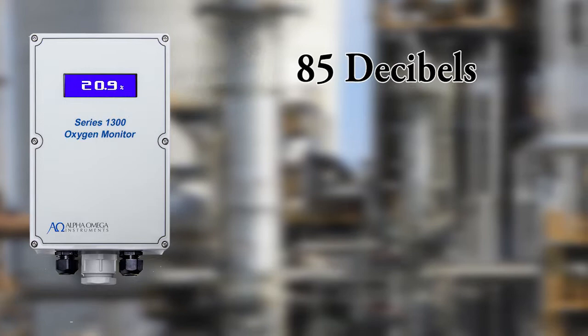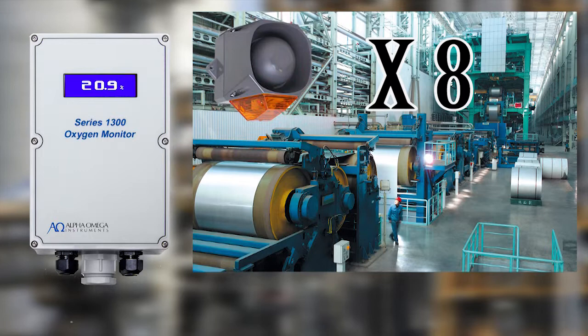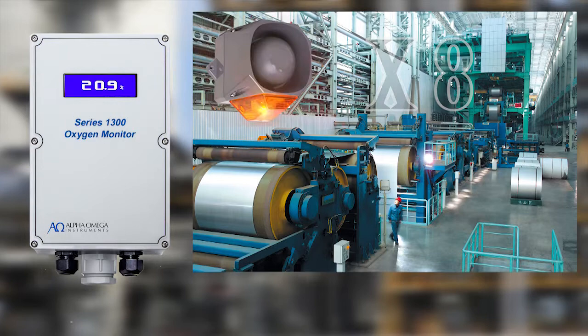If distance or environmental background noise is a concern, the Series 1300 Oxygen Deficiency Monitor can control up to 8 optional horn and strobe alarm enunciators. When using horn and strobes, the instrument can be easily programmed to activate either the horn or strobe portions individually, depending on user preference. Included with the Series 1300 are 2 sensor-assignable analog 4-20 mA DC outputs.